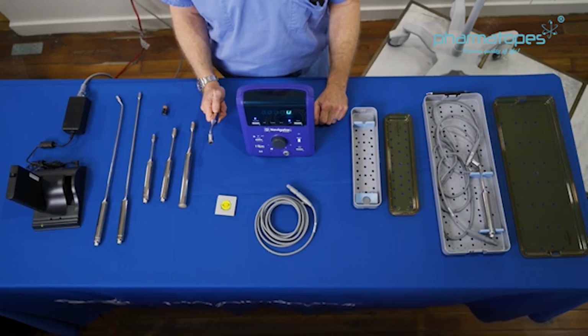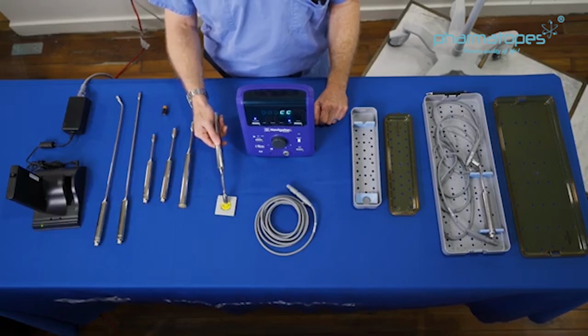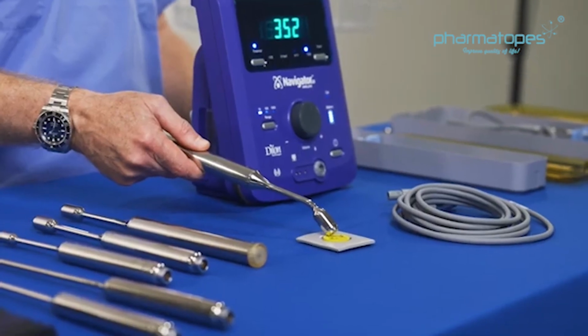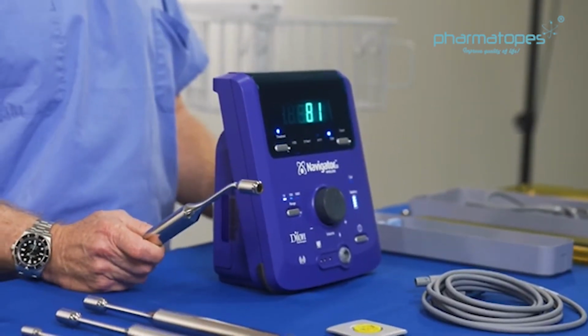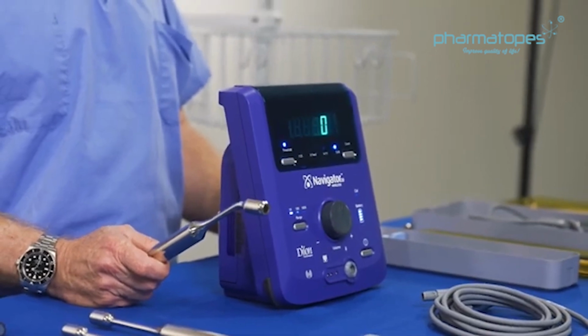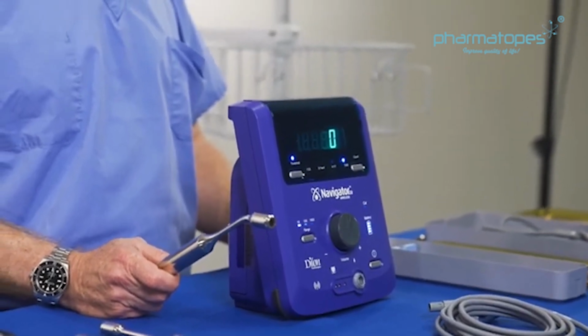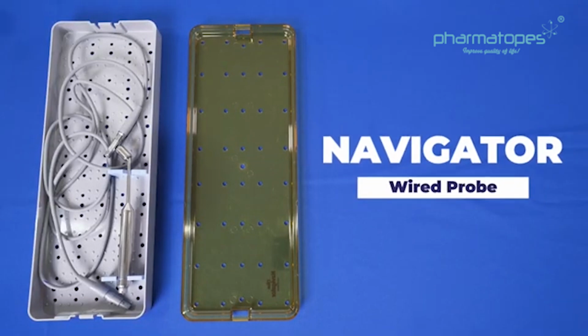The wireless probe has a self-calibrating mechanism, so all you need is to make sure the probe is reading counts. The exact number of the counts does not matter because it is dependent on the activity of the radiation source at hand. In order to comply with standards of various accrediting organizations, such as Joint Commission and the CDC, critical devices such as surgical gamma probes are sterilized at central processing.